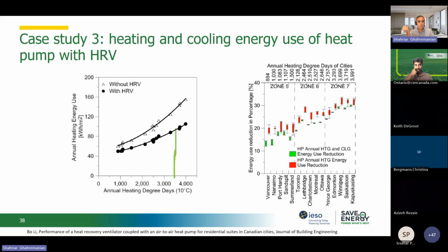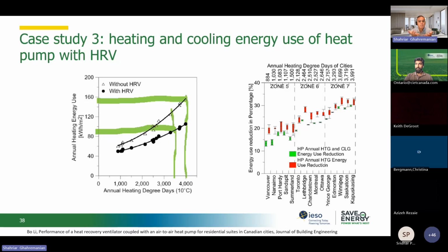Or if we go to a colder climate, let's say 4,000 heating degree days, then these two lines that you see show heat pump with heat recovery ventilator and heat pump without. And then you see that this is the annual heating energy that is needed. So this is with heat recovery. This is without. So we are talking around, let's say, 90 kilowatt hours per square meter versus 150 kilowatt hours per square meter. So that's the amount of heat that was recovered by our ventilator, and then the heat pump took advantage of that one. Again, we don't have that much time to go through this one.